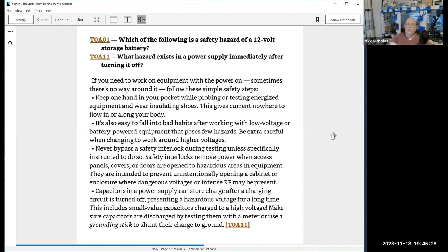Number one, you don't know the insulative capacity of your shoes—don't bet your life on it. Don't bet your life on the insulative rating of tools unless they're specifically designed for high voltage electrical testing. Don't use probes or testers that are homemade and aren't rated for voltages high enough that the insulation will protect you. They've got to be not what you think, but actual tested rated values.